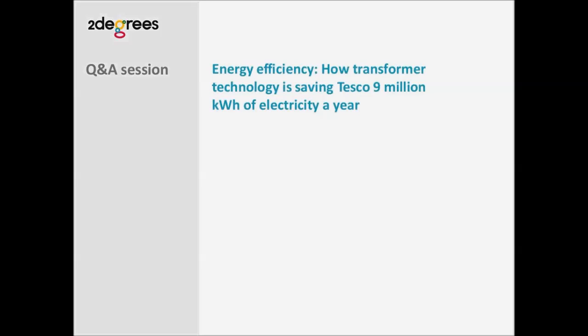That's based on 70% load at sort of 9p or whatever per kilowatt hour. If you're wanting to retrofit and change an existing transformer out and you're benefiting from voltage optimization, clients in the past have had payback inclusive of the installation, the cabling and the monitoring in 12 months. Now, that was an excellent result, so it can be upwards of 12 months, but that's the best result we've had so far. That's for full capital expenditure.